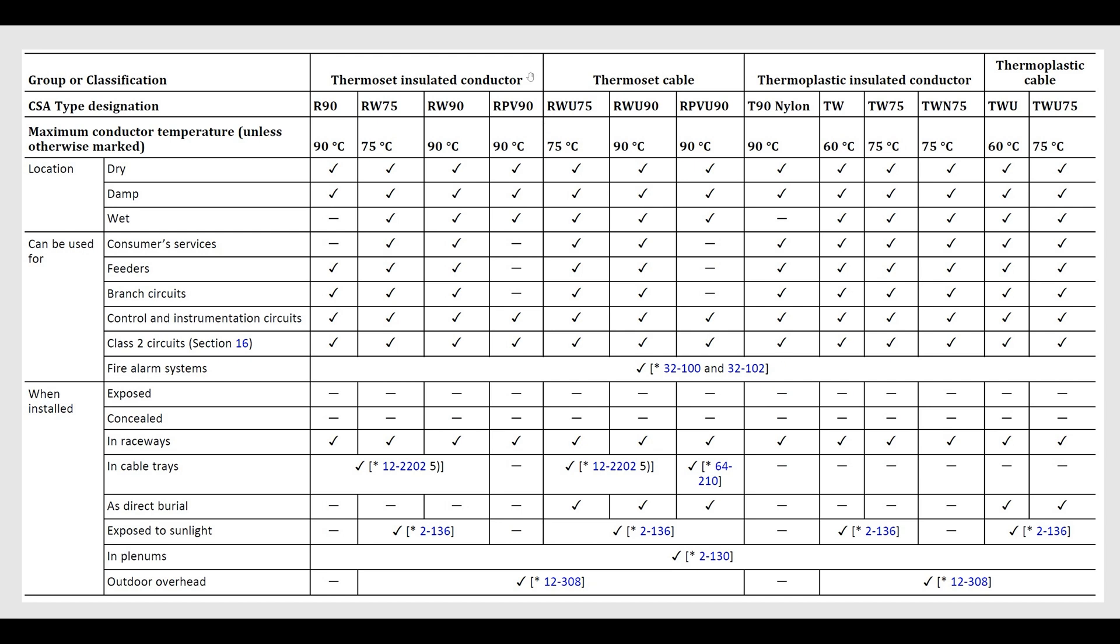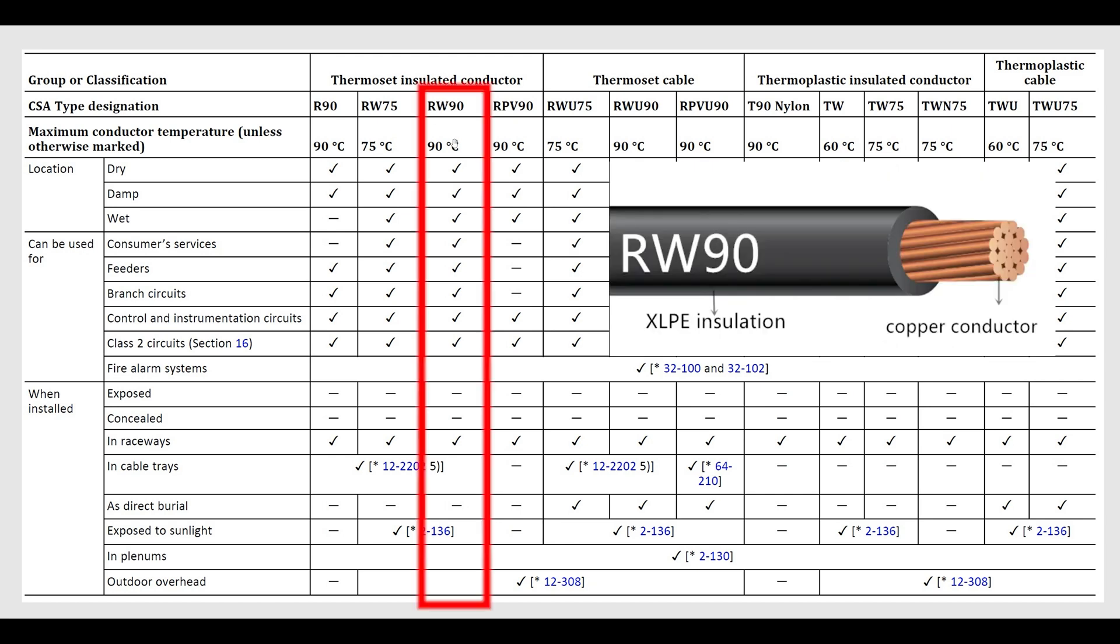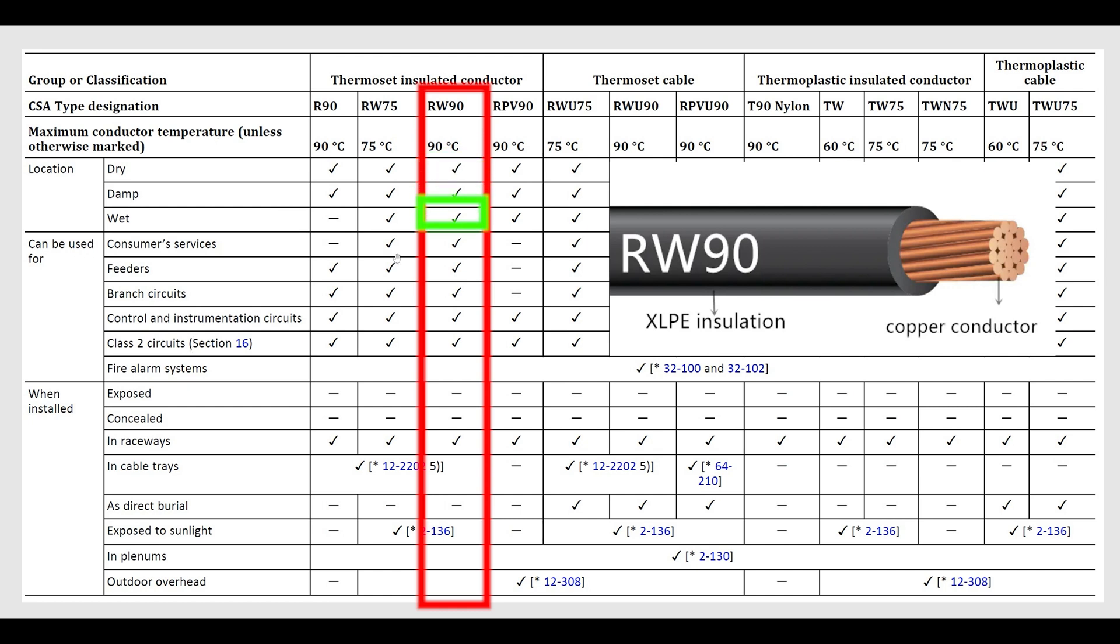So first thing, let's talk about RW90. Pretty common stuff. You see it right here and it's got checkmarks where you're allowed to use it: dry, damp, wet, 90 degree rated—that's the maximum conductor temperature. Of course, unless otherwise marked, it can be used for consumer services, feeders, branch circuits, control, class two.